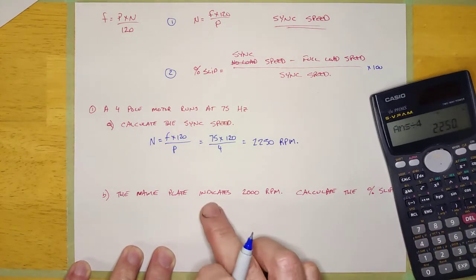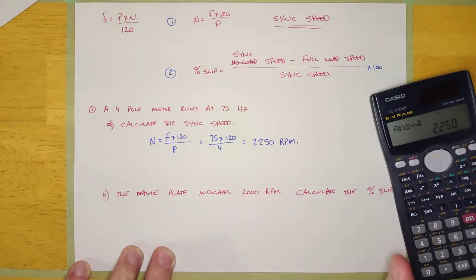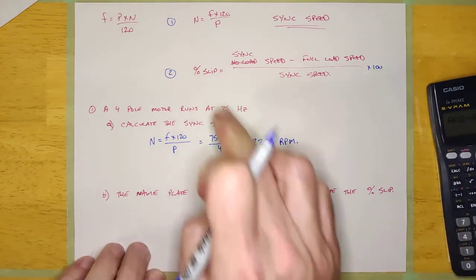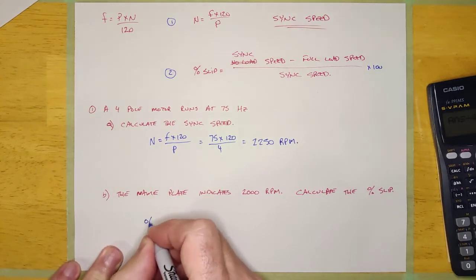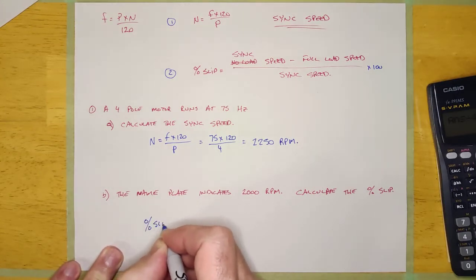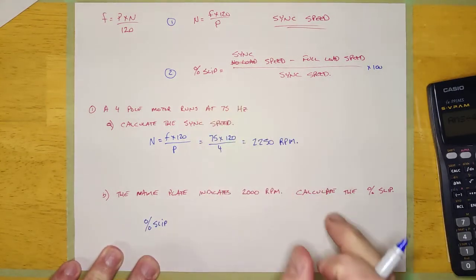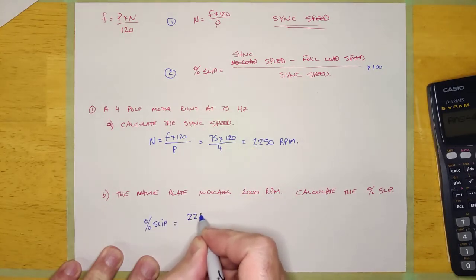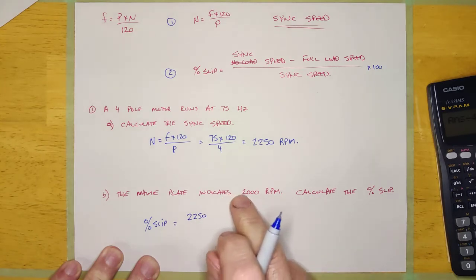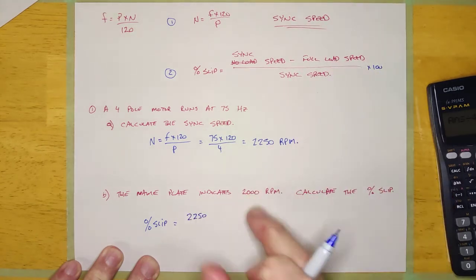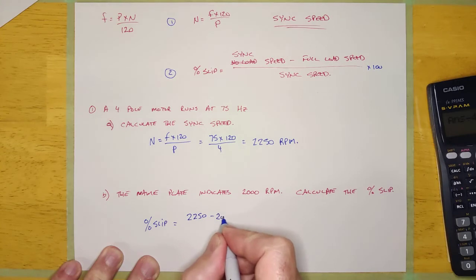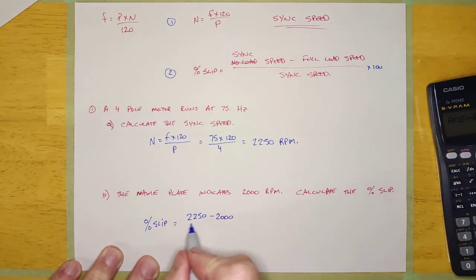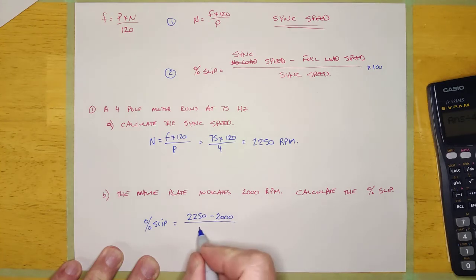Now this same motor, the nameplate indicates it runs at 2,000 RPM. Calculate the percent slip. So let's do that. We're going to use this formula right here. Percent slip, well, it should be the sync speed, which we just calculated. 2250 minus the full load speed or actual speed. In other words, this is going to calculate the amount it's slipping, and then we're going to divide it by the sync speed.